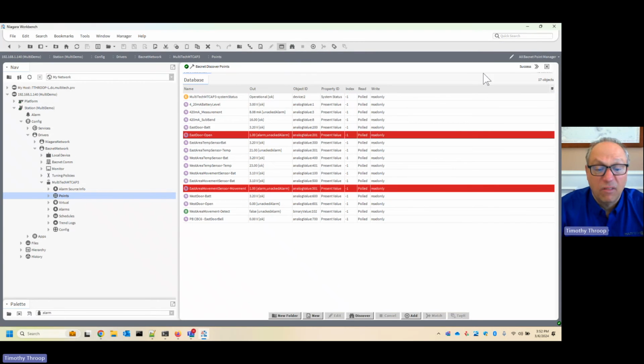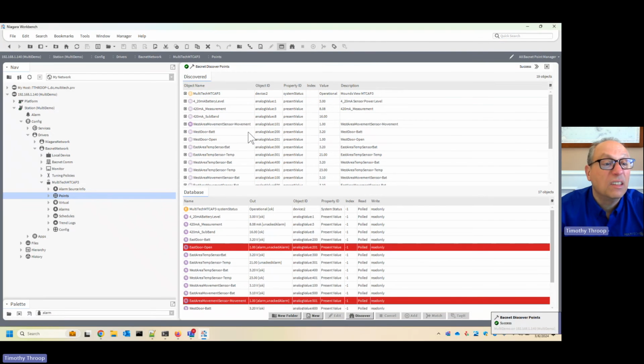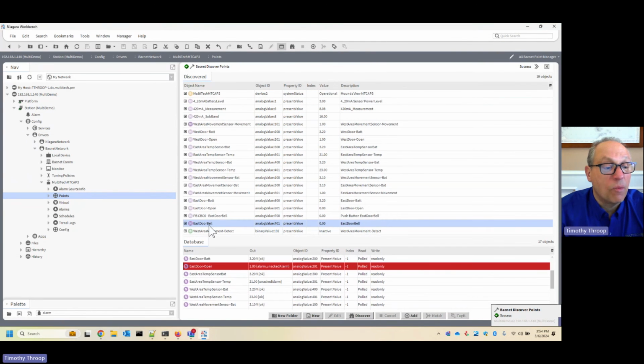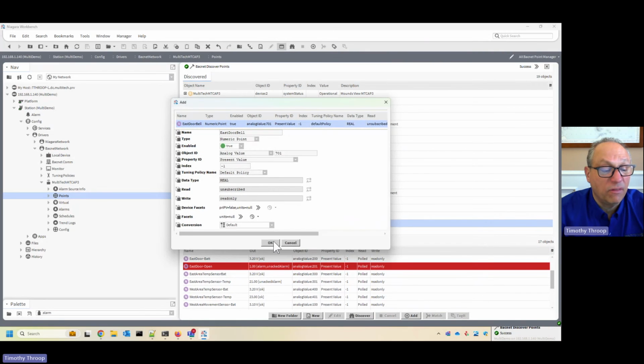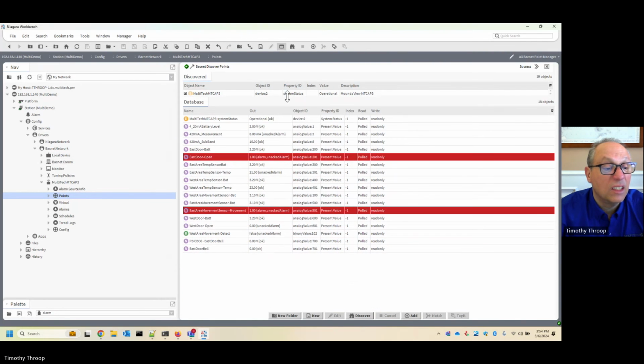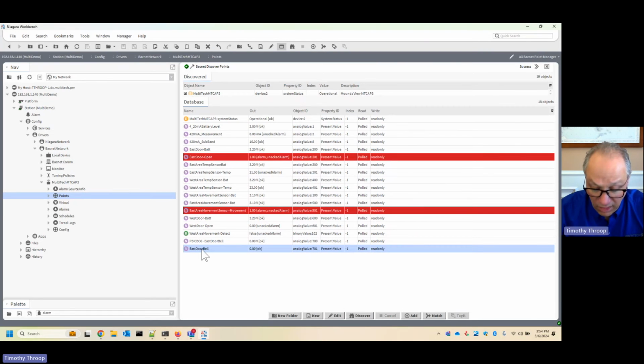Back to our BACnet system, we're going to rediscover all of those points, and we should see doorbell button event function. And there it is — by hitting the button, that should turn that to a 1, indicating that the button has been pressed. And there it goes. So 0 means hasn't been pressed, 1 means it has been pressed, and you can also send additional, more specific data about how long it's been pressed and so forth.